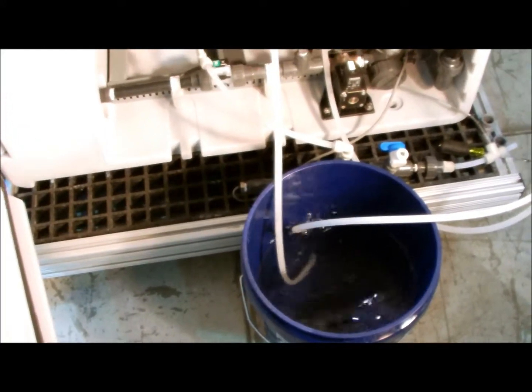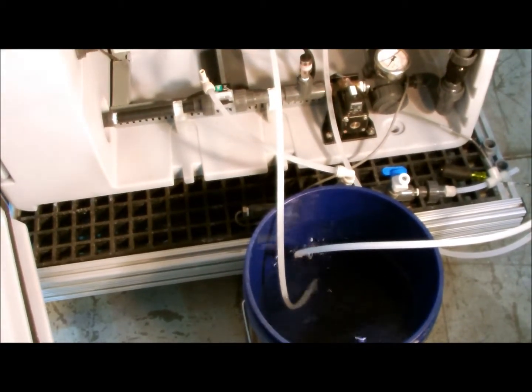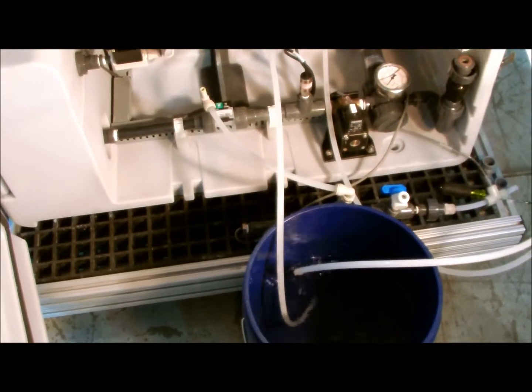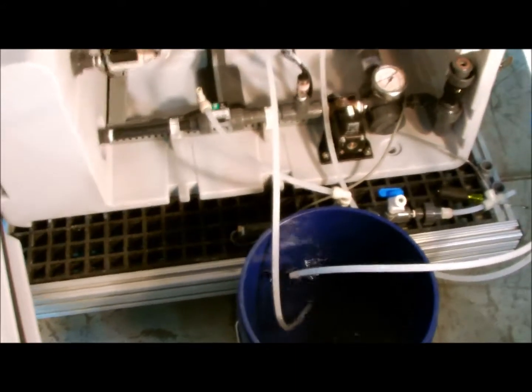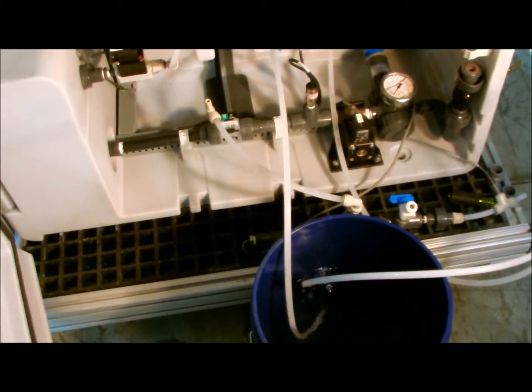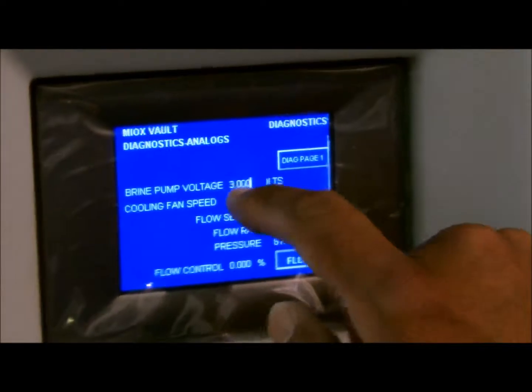Allow the pump to circulate the acid water mixture for about 25 to 30 minutes, longer — upwards of 50 to 60 minutes — if using a weaker acid solution or if the cell is heavily calcified.